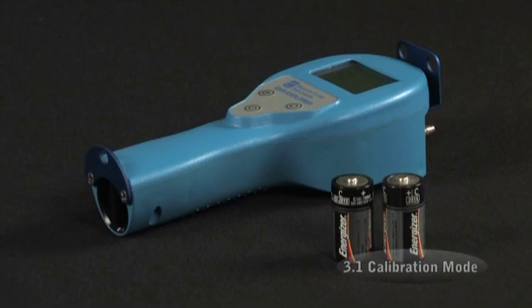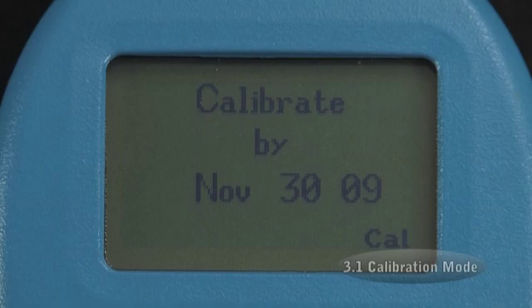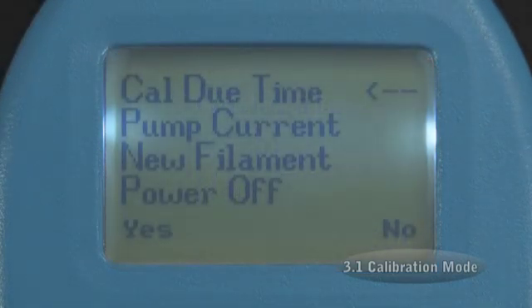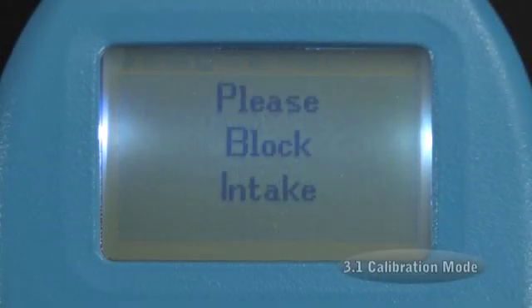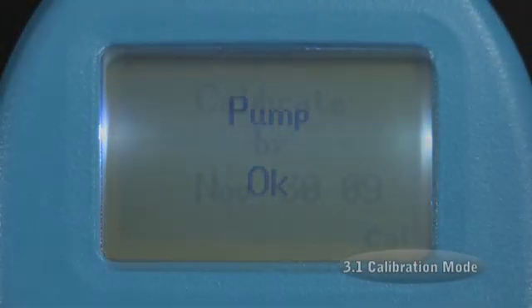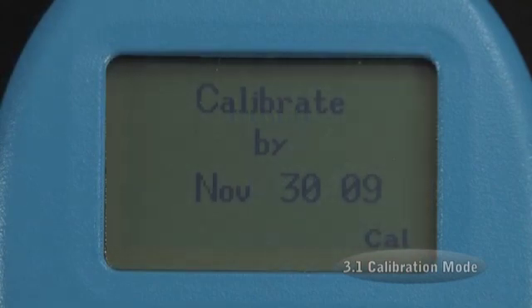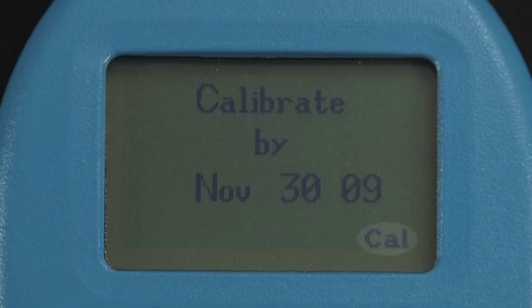We recommend that you calibrate your Explorer as frequently as possible and at least every 30 days. If your company requires more frequent calibration, you can adjust the built-in reminder accordingly. You do not need to have a filter attached to perform a calibration. Turn the unit on and, when prompted, block the intake. After you receive the Pump OK message, the Calibrate By screen will appear. You must be ready to quickly press the right button under the word CAL, because this option will only appear for about 4 seconds unless the Explorer is overdue for calibration.